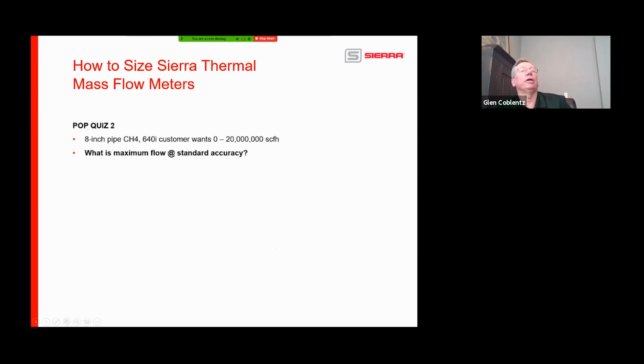All right, last one. This is for all of our flare gas applications that we deal with every day. 8-inch pipe, methane, 640i. Customer wants 20 million standard cubic feet. That should be per day, folks. We missed that. This is per day. Standard cubic feet per day, not per hour, per day. What's the maximum flow at standard accuracy? Unit of measure will be standard cubic feet per day that I'm looking for.